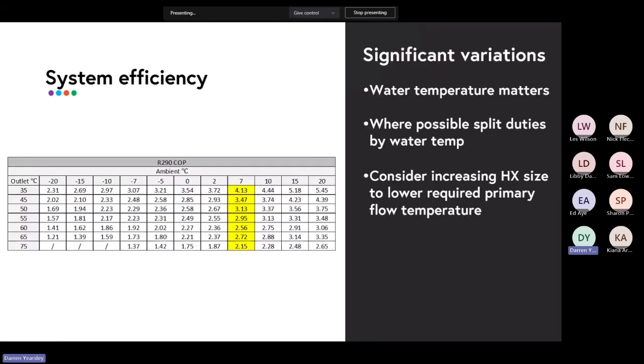Okay, so just a word on system efficiency. Just because you can doesn't mean you should. The efficiency of the appliance is very much tied to 2 things: what the outside ambient temperature is and what primary flow the heat pump is producing. You can see the highlighted row there to contrast this. At a 7-degree outdoor, going from a 75-degree flow temperature with a COP of 2.15, exact same appliance, exact same conditions, but with a 35-degree flow temperature, almost double the efficiency, so 4.1. So it gives you an idea of just how important it is to think about what you're going to use your appliance for, and if you've got any scope to lower the water temperature.